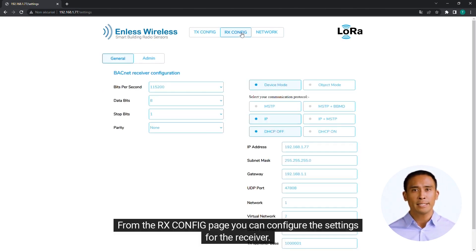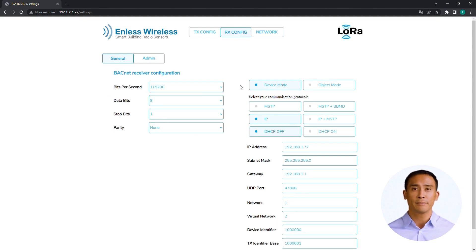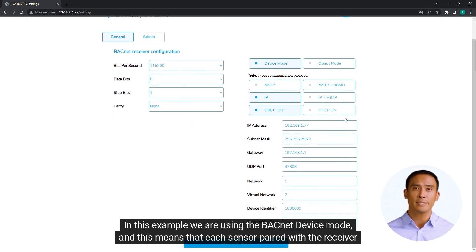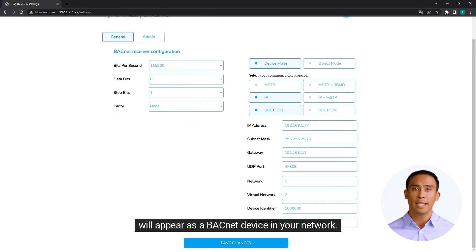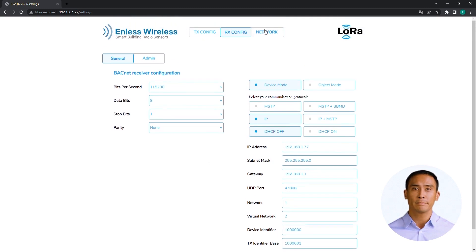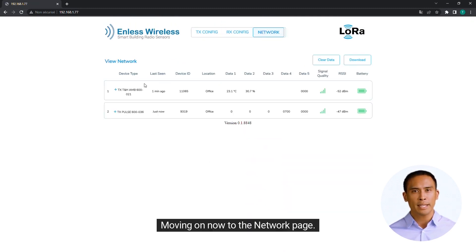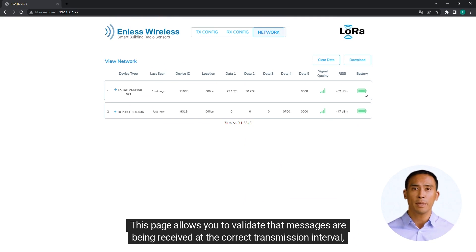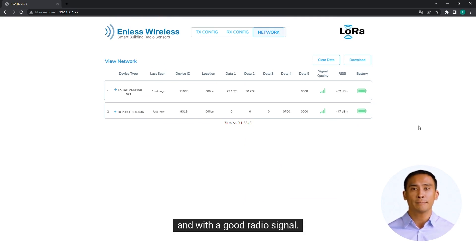From the RX-CONFIG page, you can configure the settings for the receiver. In this example, we are using the BACnet device mode, and this means that each sensor paired with the receiver will appear as a BACnet device in your network. Moving on to the Network page — this page allows you to validate that messages are being received at the correct transmission interval and with a good radio signal.